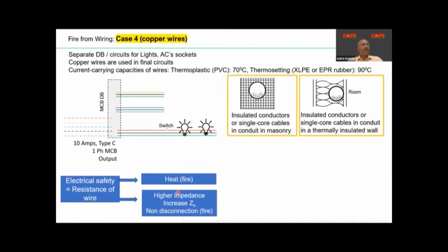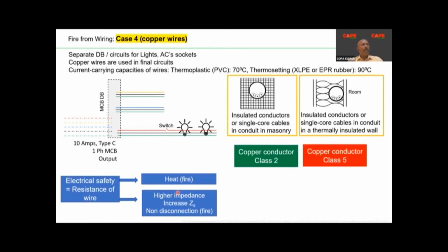If the MCB tripped, then there is no fire, only a spark. Immediately the MCB trips, so there is no fire. It's very safe. Now, if you use a wrong wire, you will be in trouble. Wires, copper wires: there are 2 types of conductors used, that means the copper conductor in the copper wire, class 2 and class 5 conductor. All the calculations in the standards consider class 2 copper wire, which has a lesser resistance in comparison to class 5 wire.